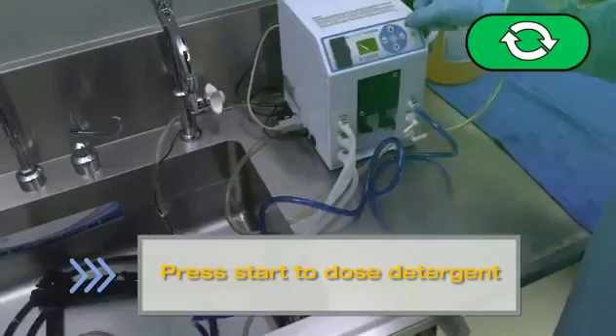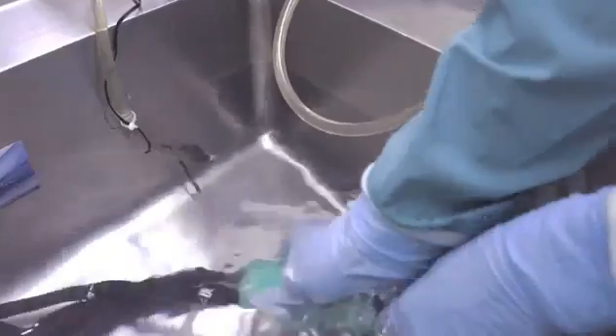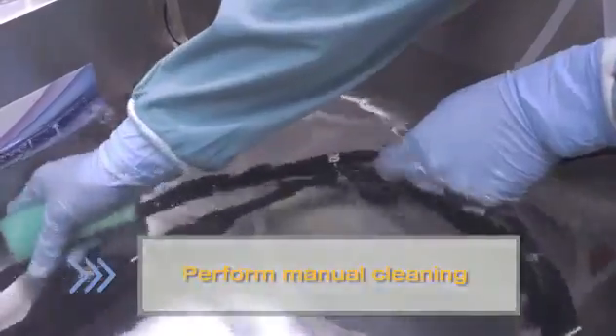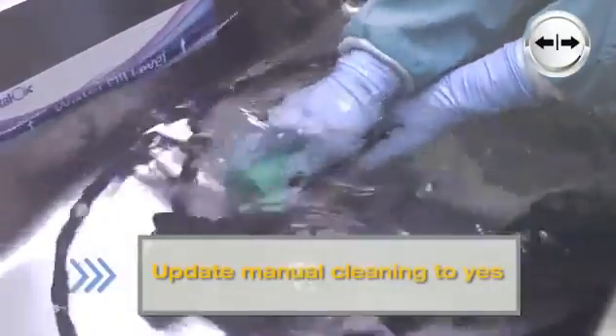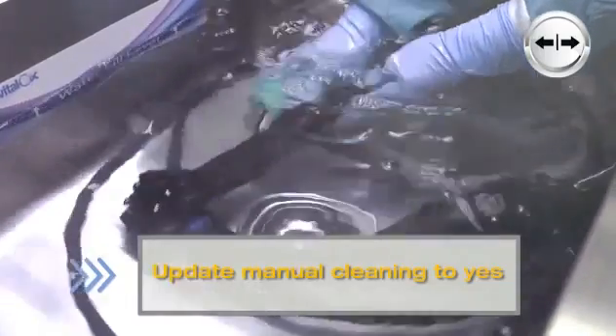Then, press Start to dose detergent. Follow the scope manufacturer's IFU and perform manual cleaning. Once complete, press the scroll button to update the manual cleaning field to Yes.